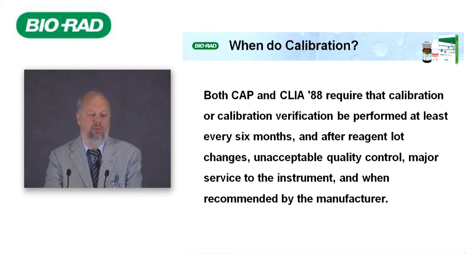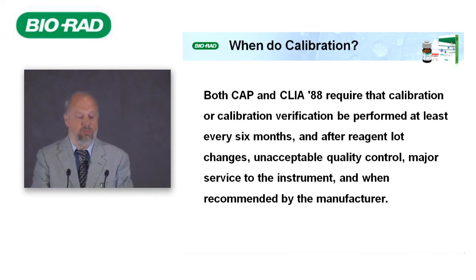Both CAP and CLIA require that calibration or calibration verification be performed at least every 6 months and after reagent lot changes. That's what most of the laboratories are not doing. Unacceptable quality control doesn't mean that you have a value which is not fitting to your limits. You have to find a reason for it before you do a calibration. These days, people very often look at the quality control result and then they do the calibration, calibrating the error away, and don't remember the error any longer. And I will show you some consequences of this.